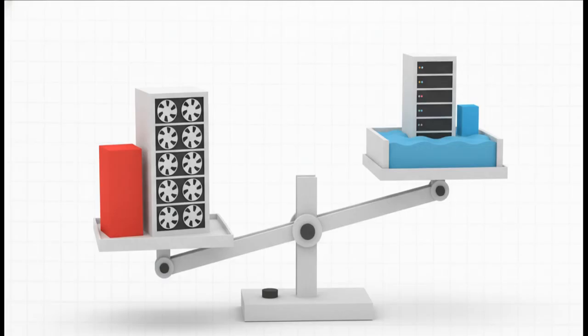But here's the inside scoop: when you calculate PUE for a normal air-cooled system, the power used by all the little fans inside the servers actually counts toward the good computing energy. But with immersion cooling, the first thing you do is rip all those fans out — you don't need them. So the whole calculation gets skewed.